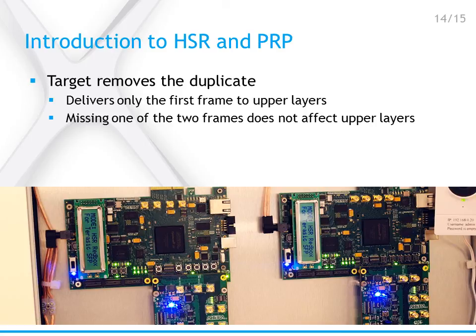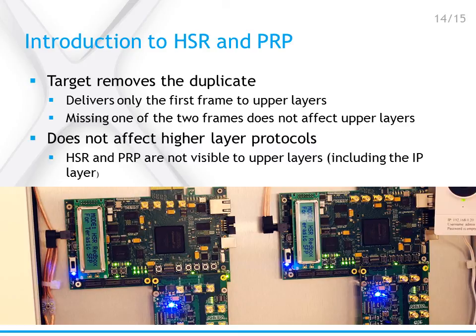In both HSR and PRP, when the two packets arrive, the destination node removes the duplicate. It only delivers the first frame to the upper layers and discards the second. This means that missing the other frame does not affect upper layers — they still get all the needed data. HSR and PRP are not visible to upper layers and do not affect them in any way, including the IP layer, so there is no need to make changes to the higher layers when implementing HSR or PRP.